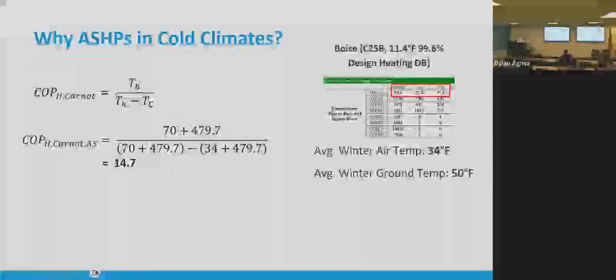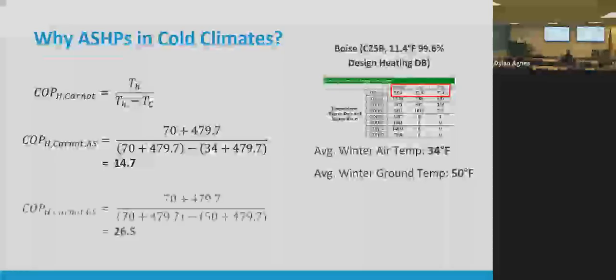We do the math on an air source. Carnot's about 14.7. That's the best you could do. Of course, we never get to the best. There are some engineering decisions and challenges. Ground source is about 26. So yeah, it's better. And I would agree in some applications, especially really big applications and really cold climates like in the Arctic and climate zone 7 and 8, once you start getting up there, it gets even more challenging to do air source. But we're working with a pretty good heat source here in this climate.